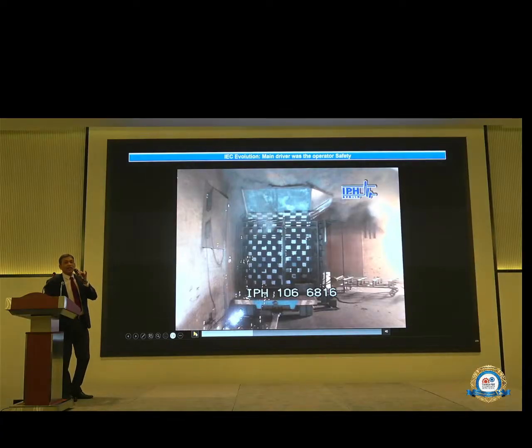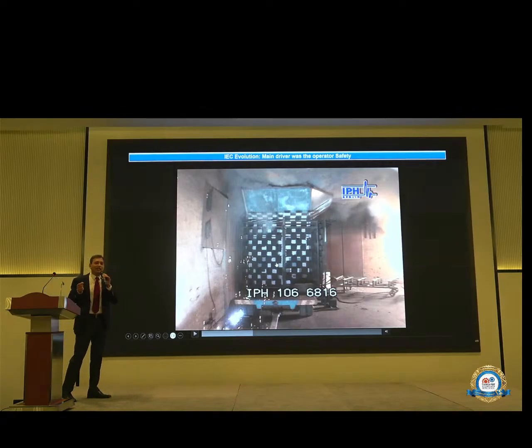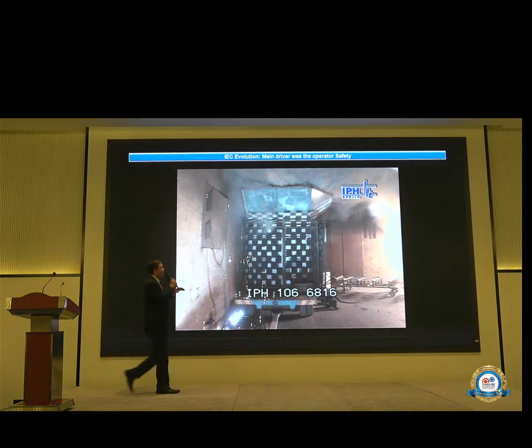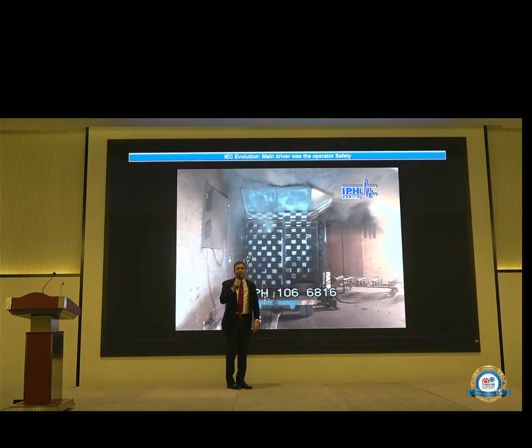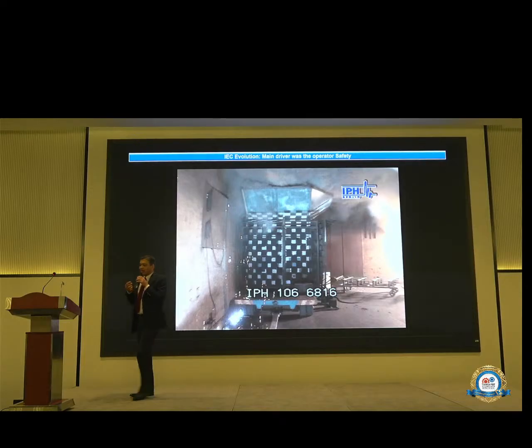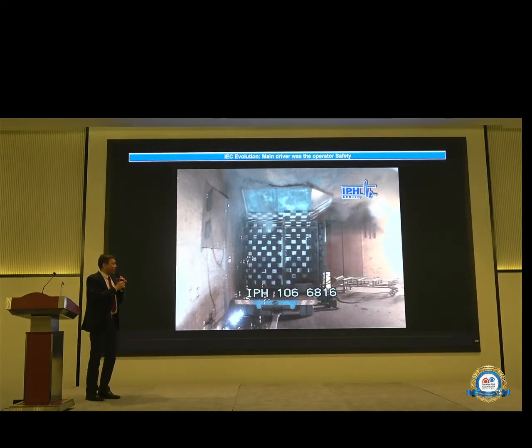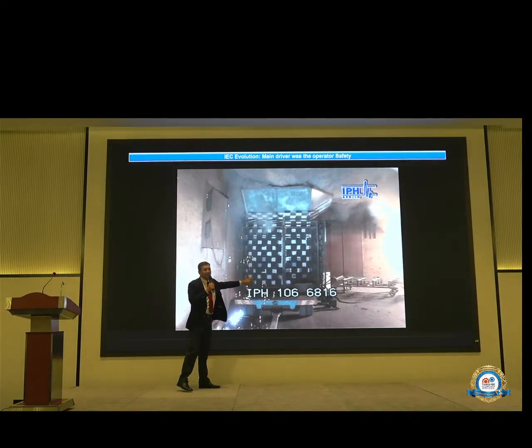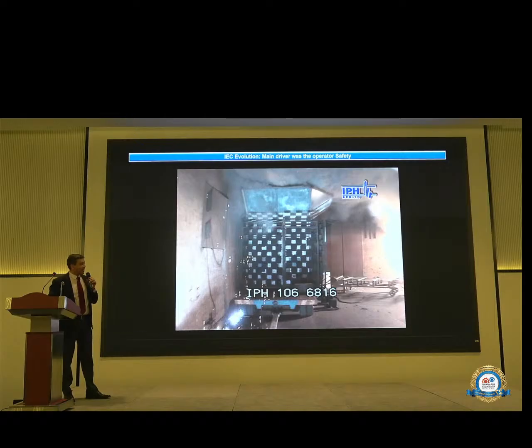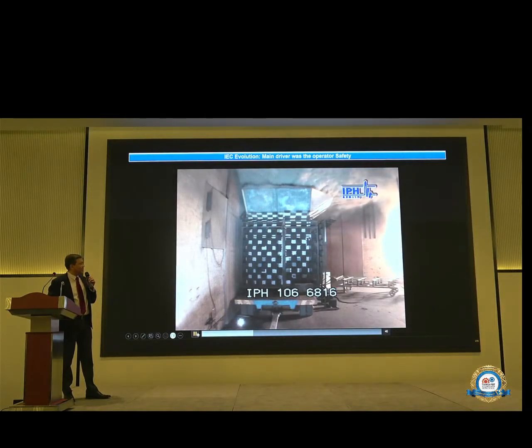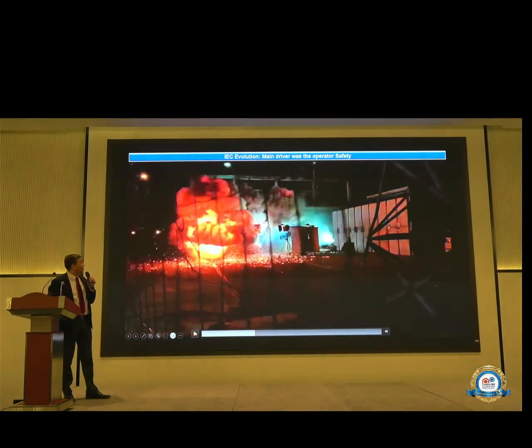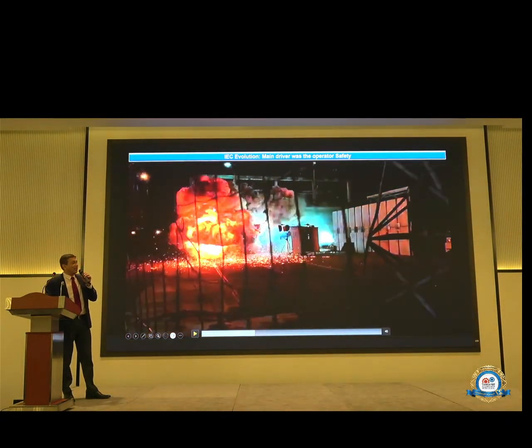This is 40 kiloampere arc handling, and you see this power. What we are doing here is creating a fault inside the circuit breaker, and this black cotton is representing an operator. These are very sensitive cloths made in Switzerland, which catch fire at even a hint of fire. So if these cloths don't burn, the switchgear is safe. These are all safety tests we are doing. But this is enormous power, as you can see. Looking at this mushroom cloud, it looks like a nuclear bomb. It is so powerful.